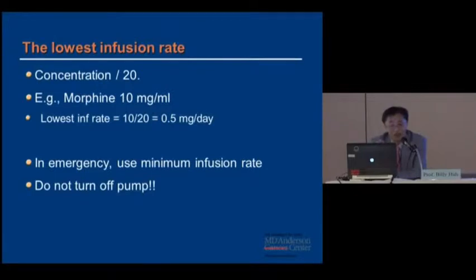You can even go lower than that using a minimum infusion rate—the pump cannot be turned off, because if you turn off the pump, you ruin it. So the pump always has to run at a minimum rate, an absolute lower limit. The minimum rate is about 10 times lower than the lowest infusion rate, which could be 0.05 milligram per day. In emergency cases, you use the minimum rate until you change the concentration, because the patient is not doing well even at the lowest rate infusion.